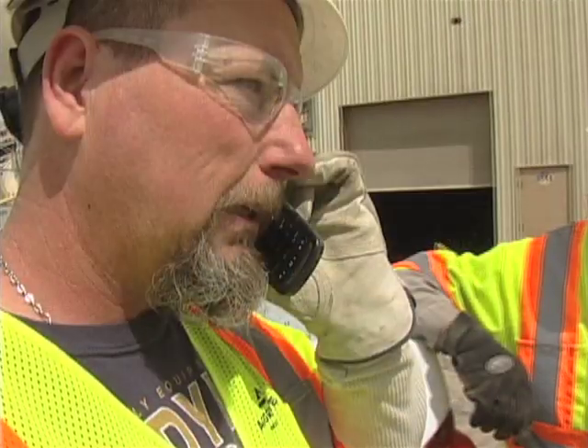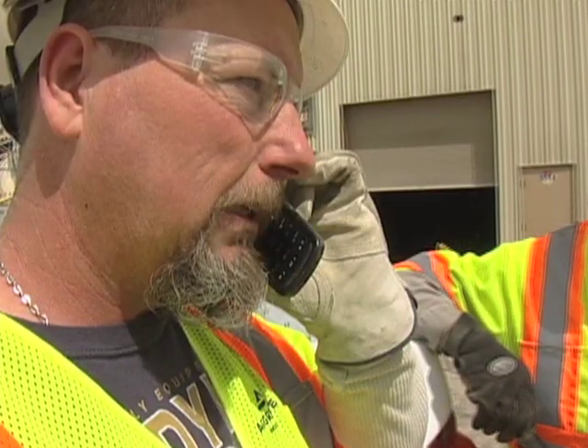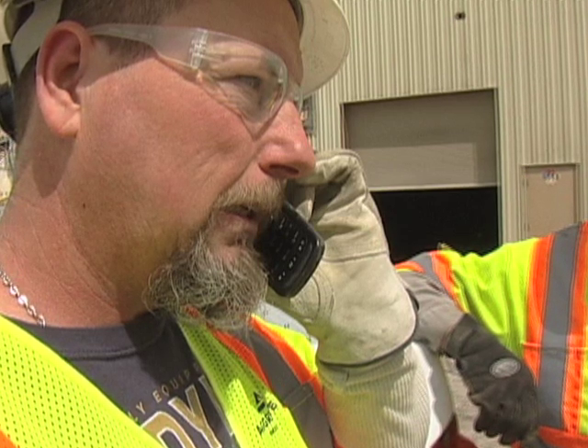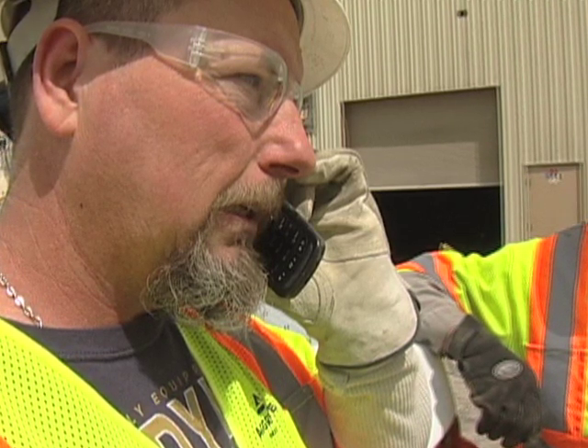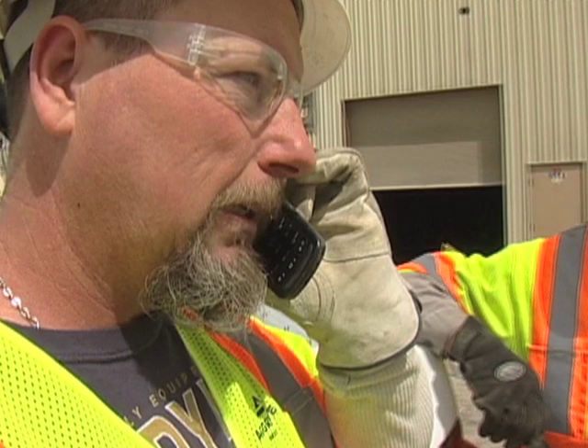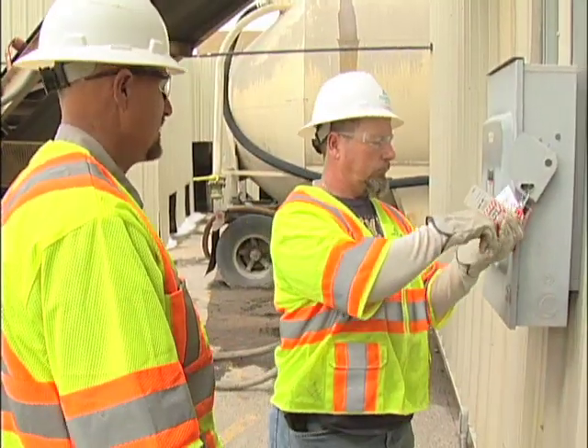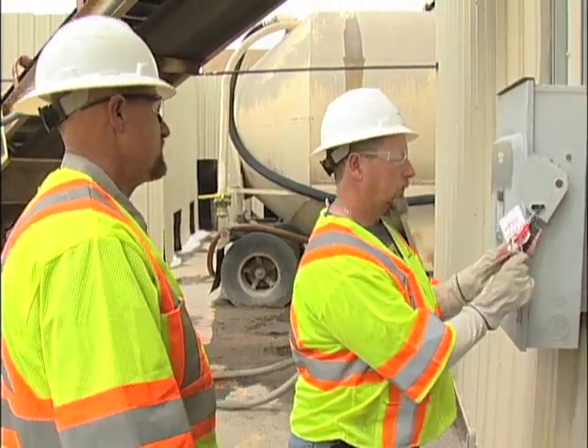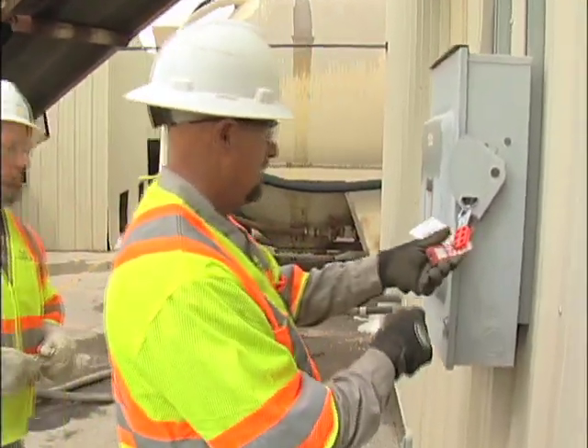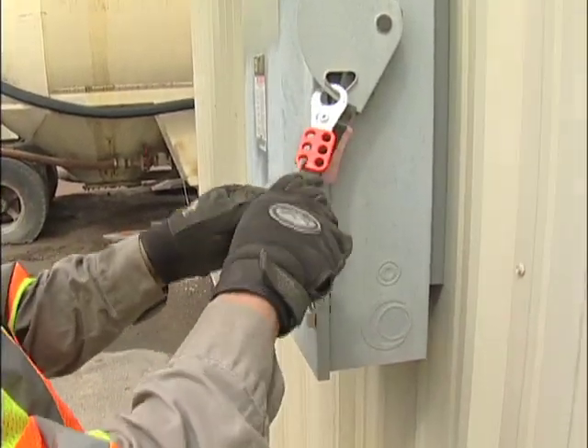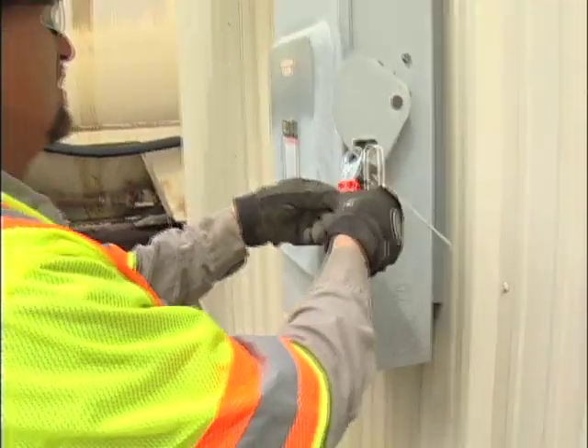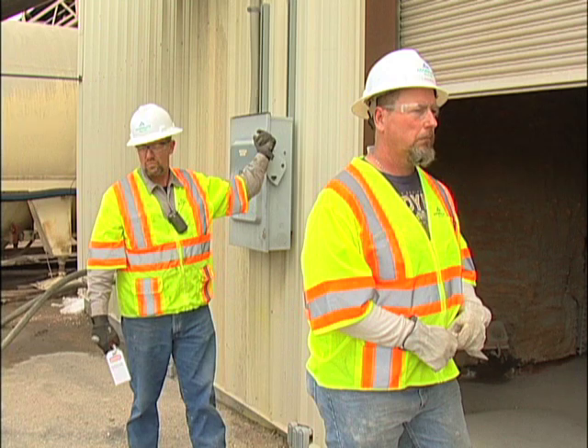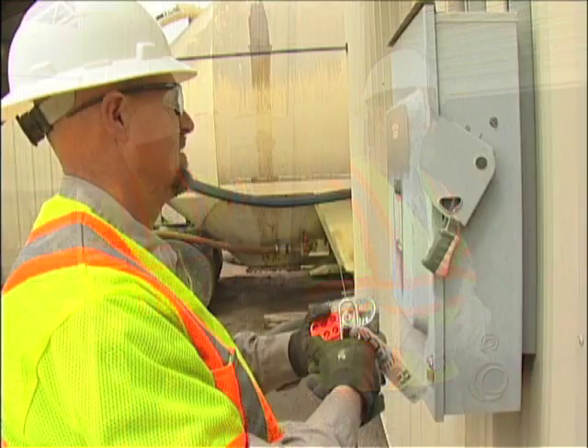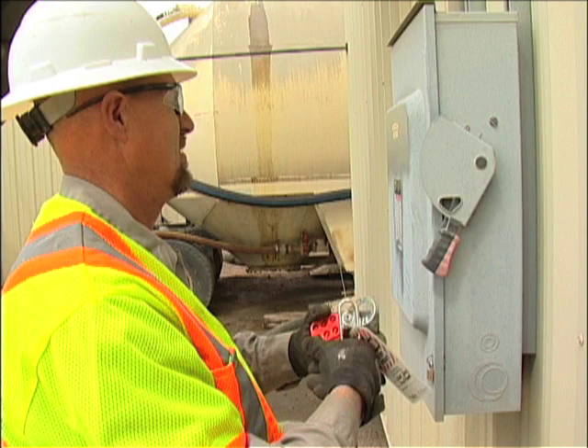D. Safely position or remove employees from the work area prior to the removal of lockout-tagout devices. Notify affected employees that lockout-tagout devices are about to be removed. After the removal of the lockout-tagout devices, notify affected employees again. Each lockout-tagout device must be removed by the employee that applied the device. Once again, check to be sure that all employees are removed and positioned out of harm's way from energy sources or equipment operation. Now, equipment may be restarted and/or tested.